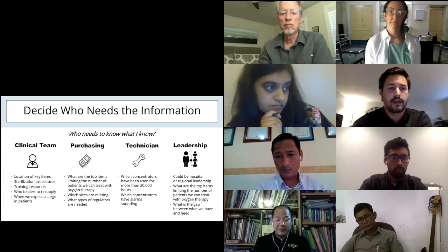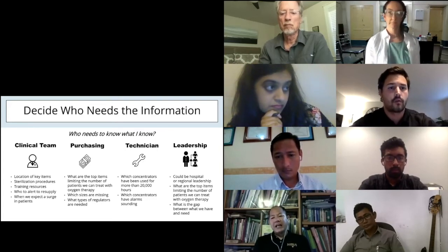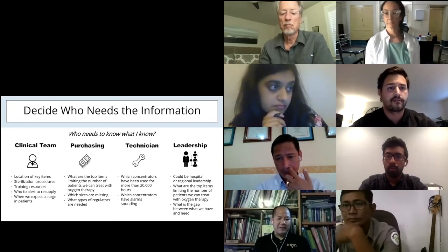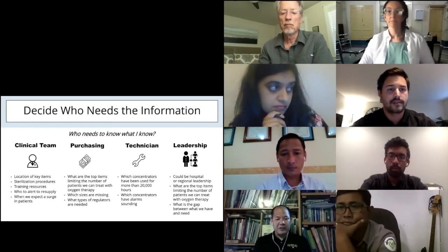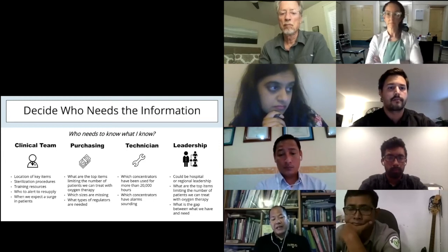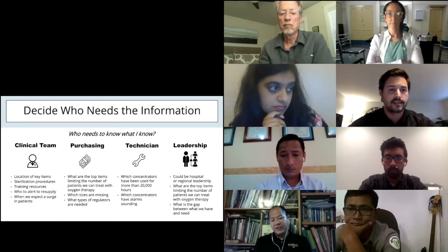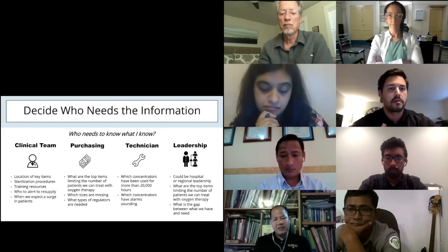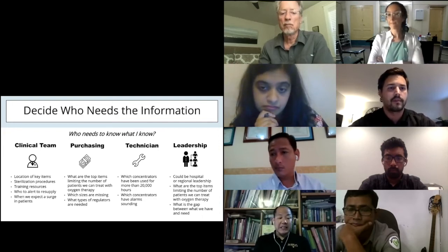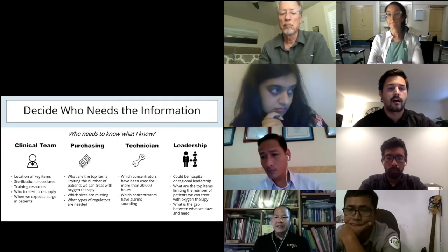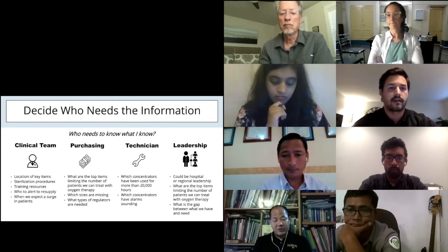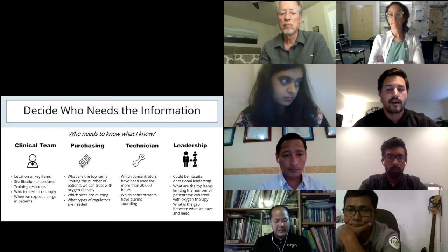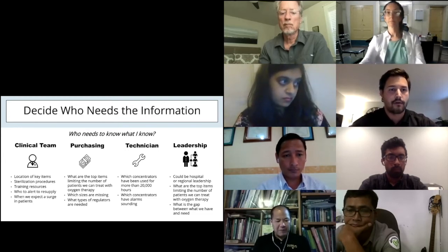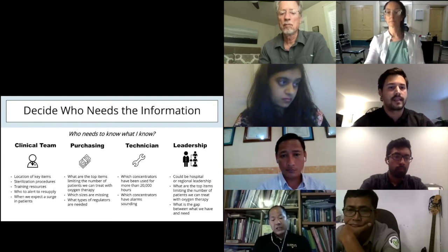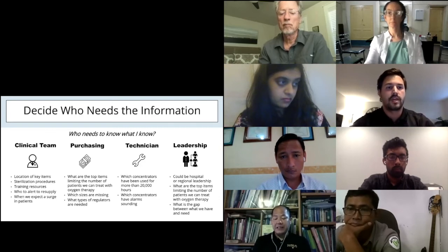Yeah, and so the alarms help know if there's something wrong with the oxygen that's coming out of the concentrator. And so when the alarm is sounding, it's saying, hey, there's not enough oxygen coming out. You need to check something. But instead of responding to that appropriately, they cut the alarm, and then now you're using this concentrator on a patient, and they're not receiving the pure amount of oxygen. And so that can definitely affect patient health simply by not telling anybody or by doing something that shouldn't be done. And so that's why it's important that you keep in constant communication.